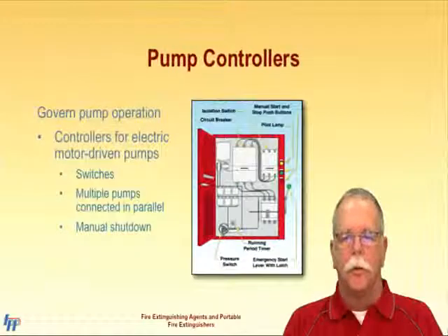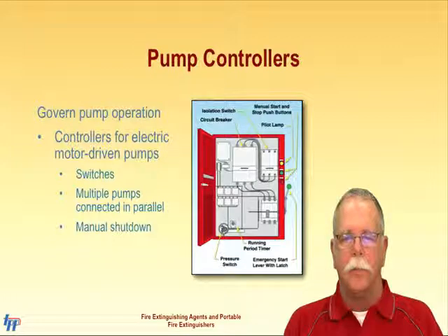The pump controller is the system of sensors and switches that starts the pump in the event that it is needed to perform. In addition to automatically starting the pump, it has provision that will allow manually starting and stopping the device for purposes of maintenance and weekly check operation. The controller is usually located in the pump room near the pump in a red cabinet.